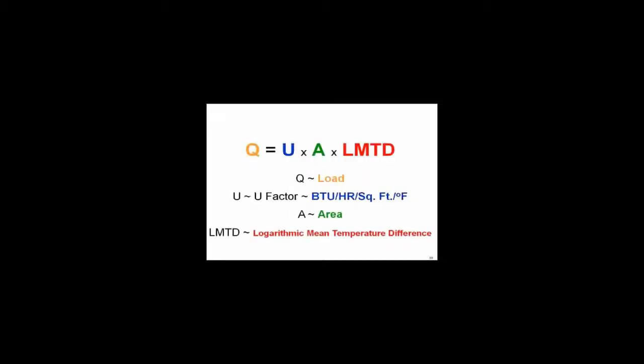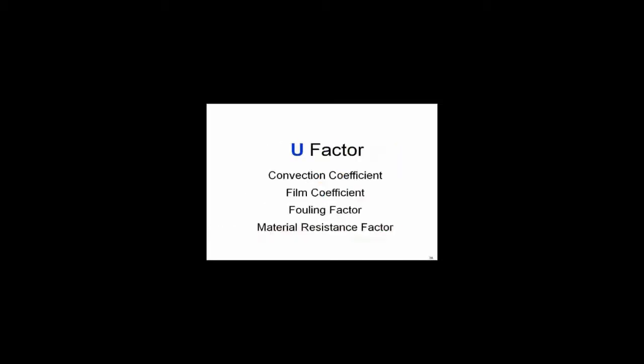So what is basic heat transfer all about? I don't care if you're talking about a cooling coil, a heating coil, chill water, hot water, or a heat exchanger. In this case we're specifically looking at heat exchangers. You've got this Q Btu per hour, which is equal to U, or the heat transfer coefficient, times the area, times the LMTD. This is kind of like the temperature differential. We've got the log mean, but that's the formula if you're a heat transfer engineer that you have to use. It's the same formula you have to use to calculate a cooling load through a wall, but we're looking at it from the standpoint of heat transfer on a heat exchanger.